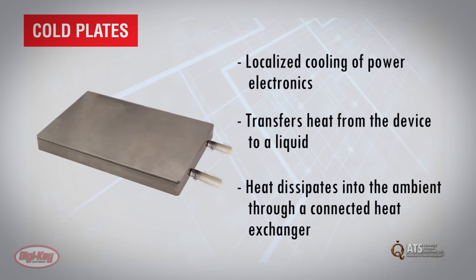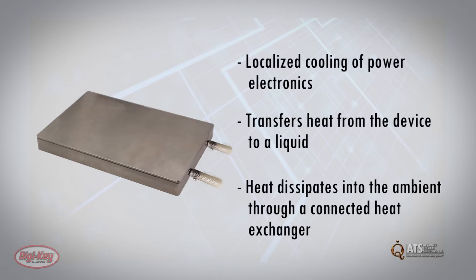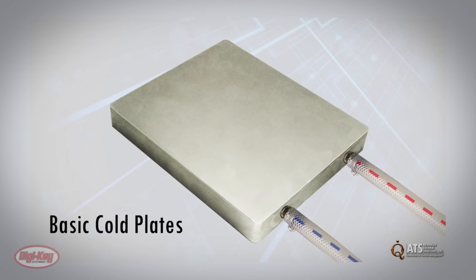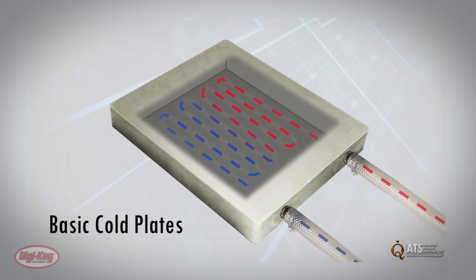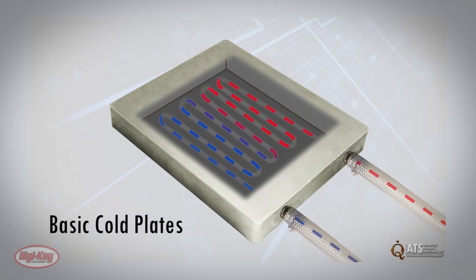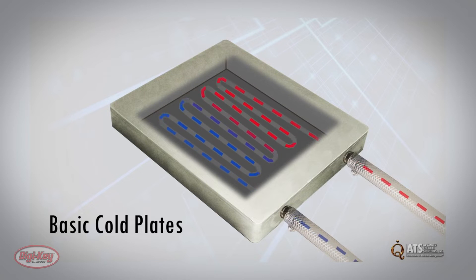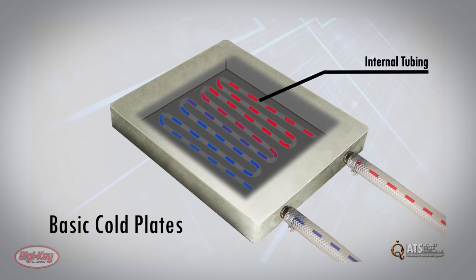One approach for thermal management is the use of cold plates. Cold plates provide localized cooling of electronics by transferring heat from a hot device to a liquid that flows to a remote heat exchanger and dissipates either into the surrounding air or to another liquid in a secondary cooling system. At their basic level, cold plates are metal blocks that have inlets, outlets, and internal tubing to allow liquid coolant to flow through.